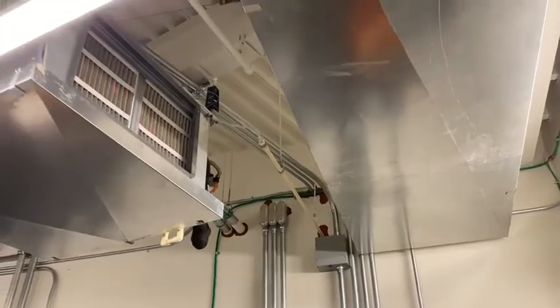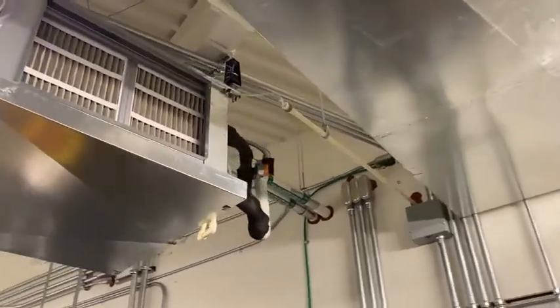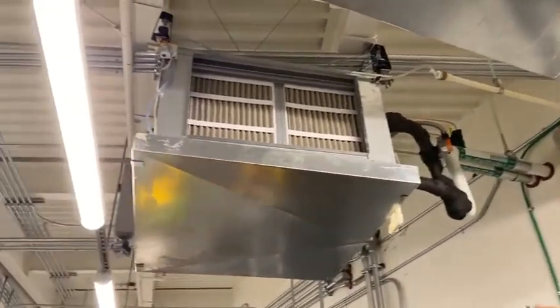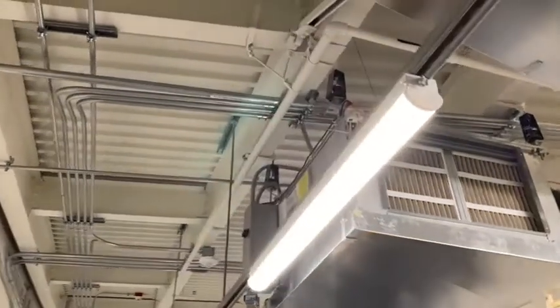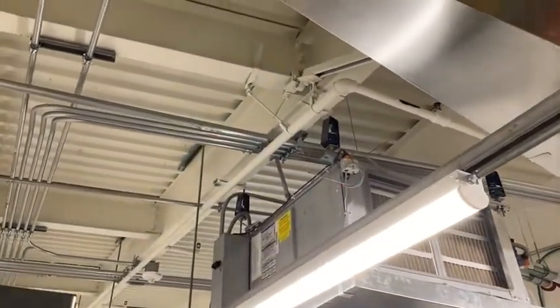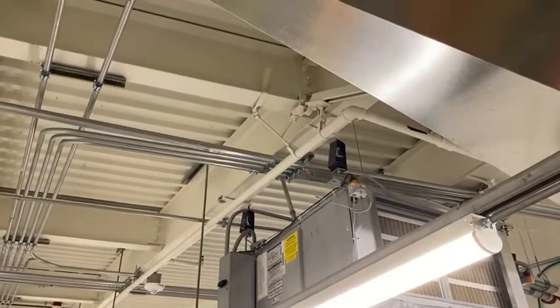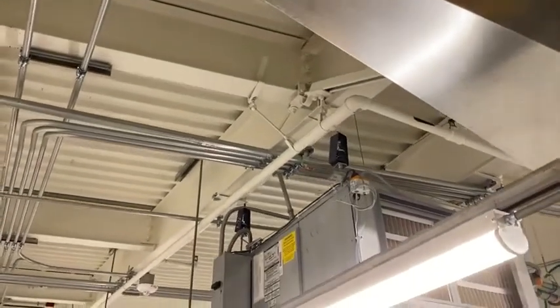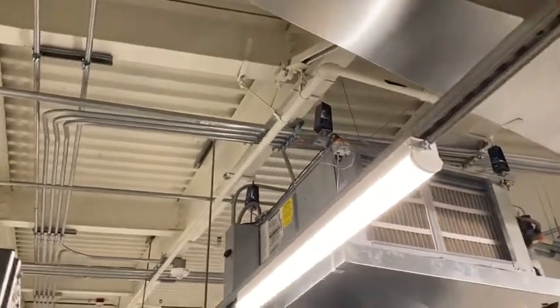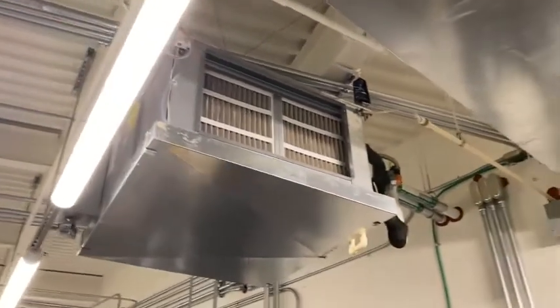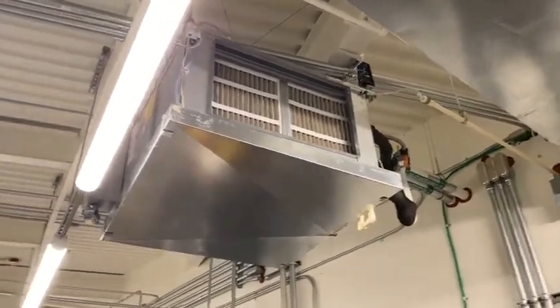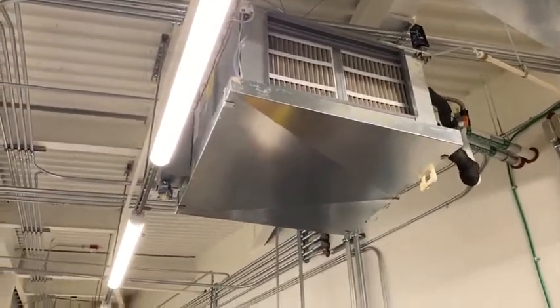Filters are here in the back. There's a filter door here, and there's a filter door on this side over here. Either one will allow you access to pull the filters out the side. There's a filter pull on all the units, like a tab at the bottom. Once you take the door off, you can pull that tab, and both filters will slide out at the same time.